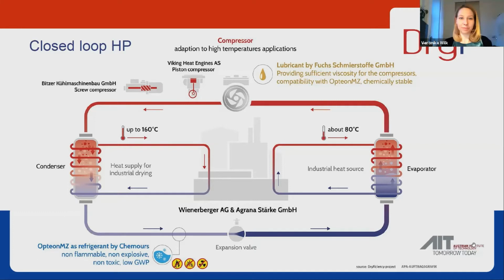Another important component of the closed loop heat pump is again the compressor. We have 2 different types of compressors for the 2 demonstrators. On one hand a screw compressor produced by Kühlmaschinenbau, a refrigerant component manufacturer based in Germany. They took their screw compressor series for industrial application and moved it to a high temperature application, checking every part for compatibility with the new conditions, and built 4 new compressors used within the DryFiciency project.